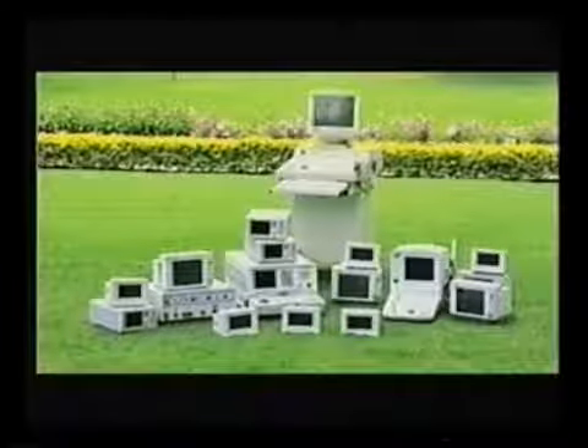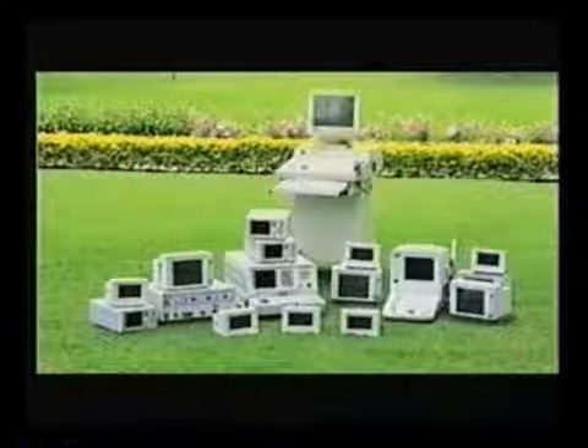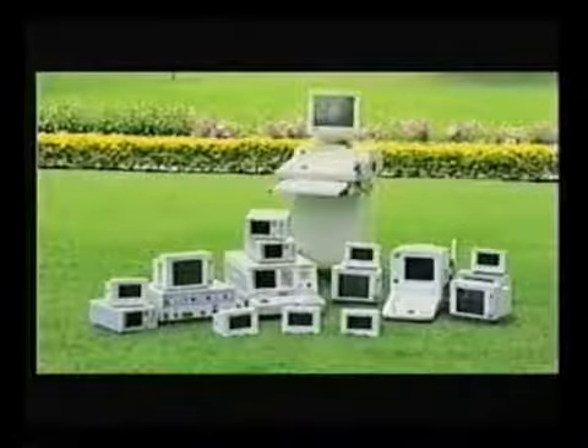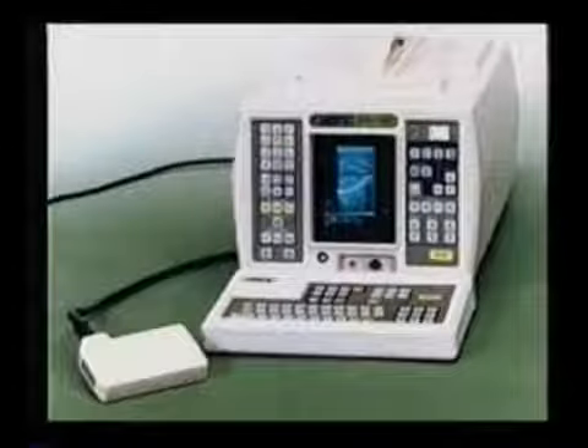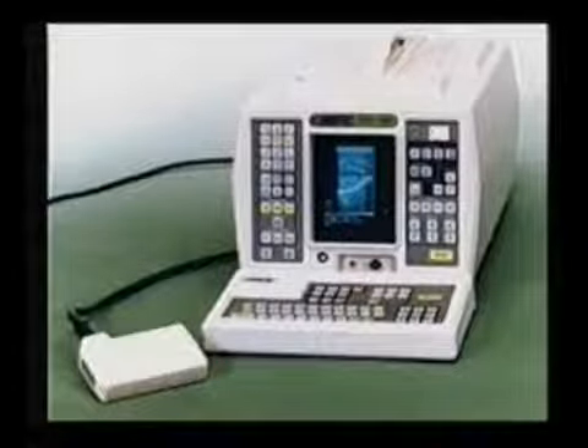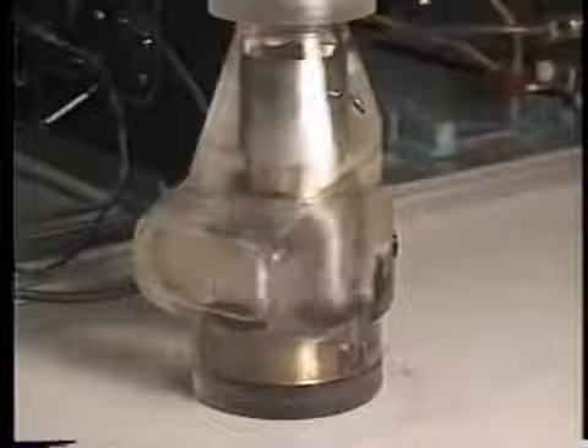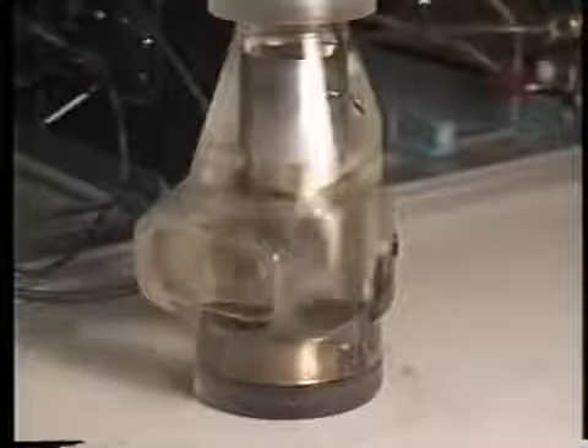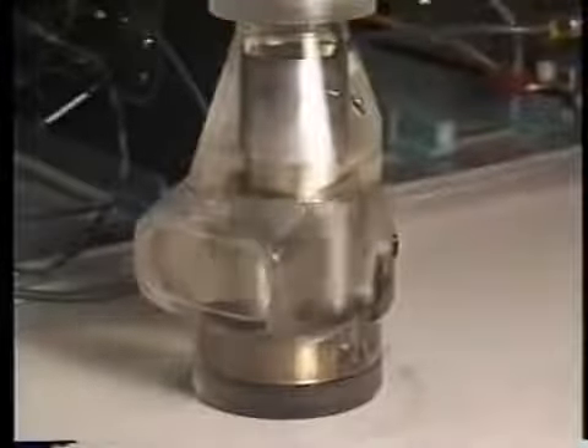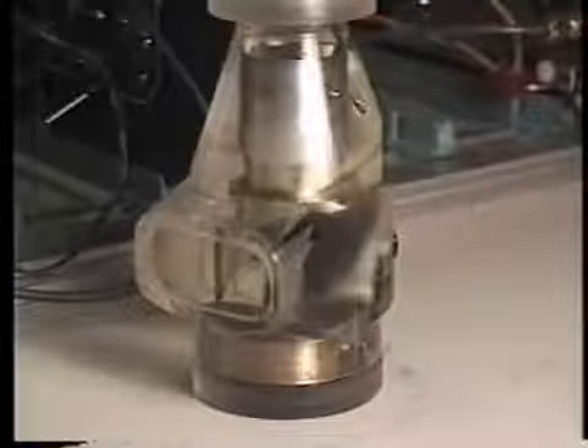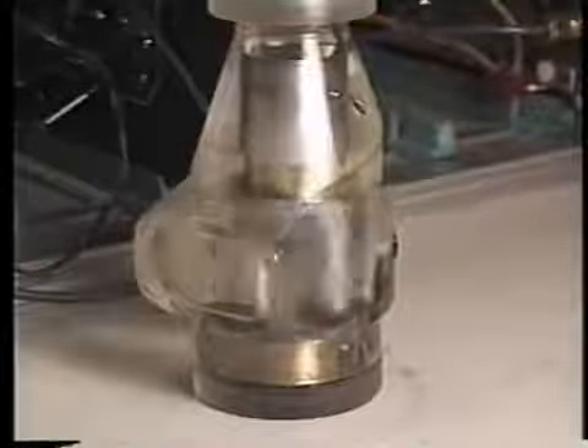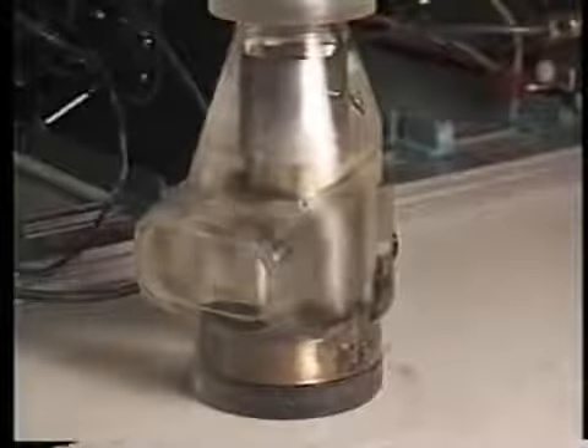Ultrasound scanners in the present market almost universally use phased arrays for scanning. These require complex processing of the signals from an array of 32 to 128 electrodes, at a substantial disadvantage in both cost and performance. The mechanical scanner utilizes one small brushless motor and only has to process the output from a few electrodes, reducing the cost of the mechanical scanner to about 1/5 the cost of a comparable phased array.